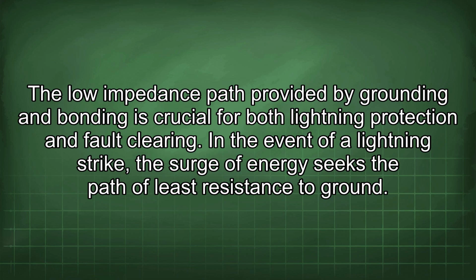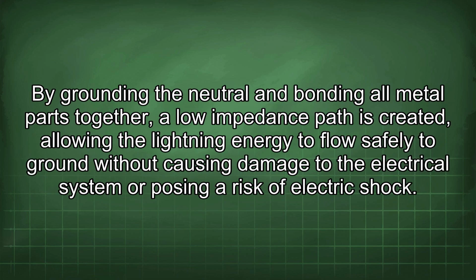In the event of a lightning strike, the surge of energy seeks the path of least resistance to ground. By grounding the neutral and bonding all metal parts together, a low impedance path is created, allowing the lightning energy to flow safely to ground without causing damage to the electrical system or posing a risk of electric shock.